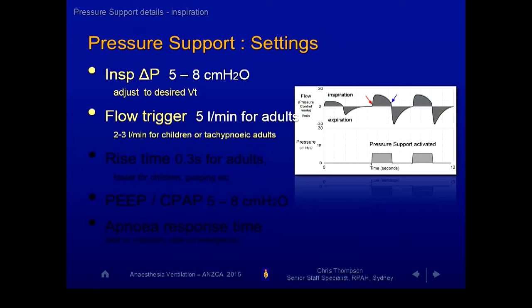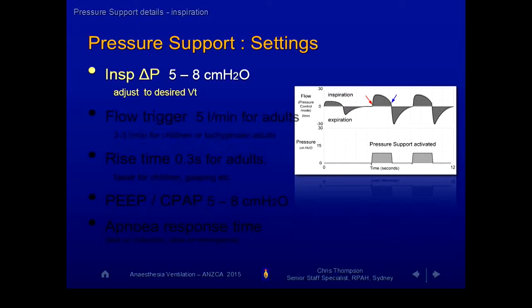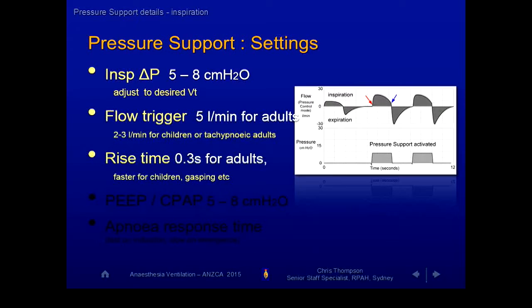But you do need to modify it only really for children. And rise time is another parameter that you will see. If you've got gasping breath, you need to get that air in quickly. If you don't, the person will try to take that breath in and be flow-starved. So you want to bring that rise time down for people who are gasping, and for children who have a high respiratory rate, it should be faster. But leave it at 0.3 for conscious people.